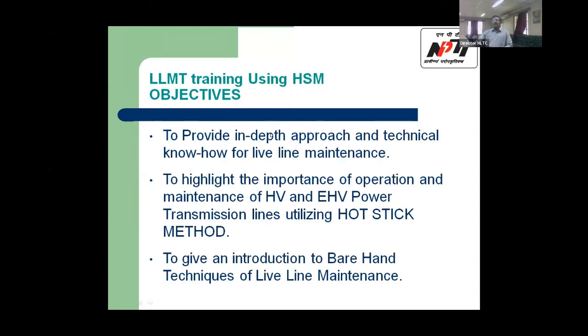Then, what are the objectives of the hot stick method? In the hot stick method, the people are working at zero potential. They will stay away from the live line, in the sense they will only be using sticks which are heavily insulated, made of epoxy glass, and they work keeping safe clearance from the energized lines. So the power is on.